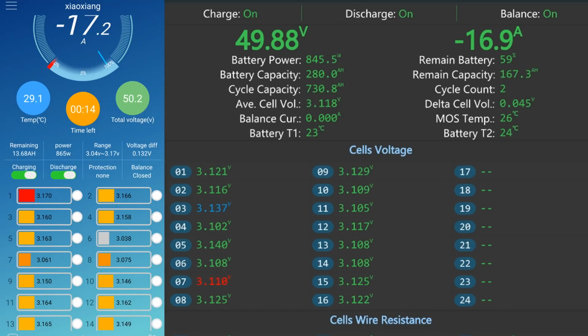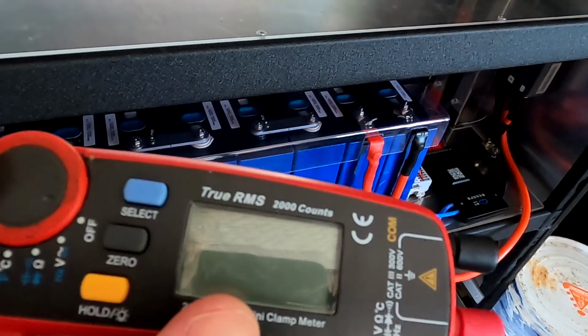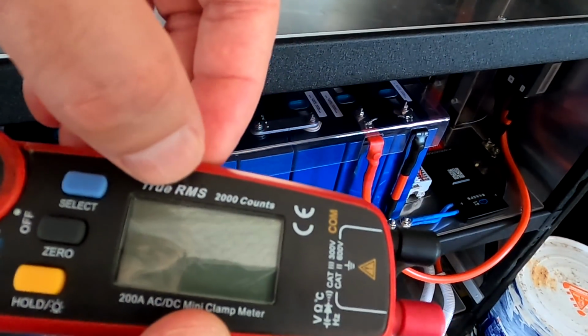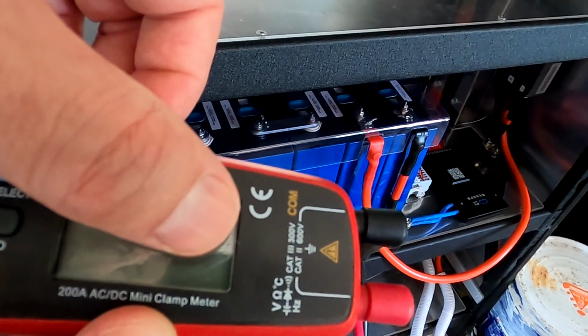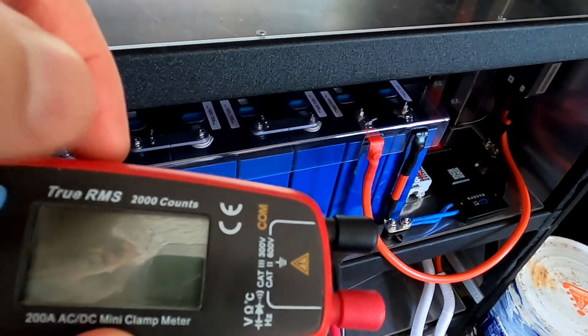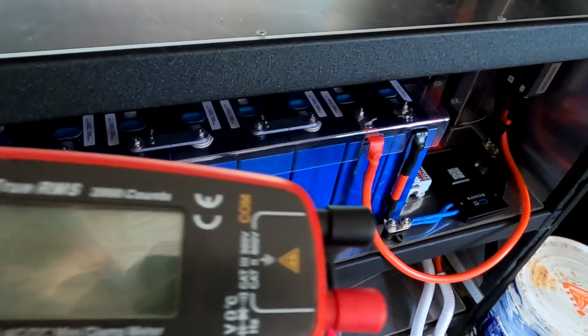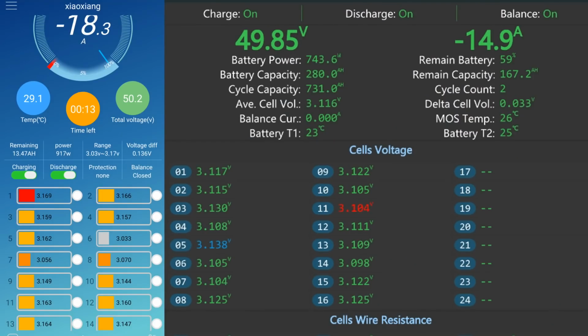Up North and Personal left a great comment under one of the last videos and explained actually why this is. It is because your normal voltmeter, your normal multimeter has true RMS, root mean square. That means this multimeter measures an average over a certain period of time and shows the value in the display. So if you have a very, very quick spike in your voltage, for example, this one will not pick it up, but will build an average. So your voltage goes up and down slowly. The JK-BMS on the other side does not have RMS measurement method. So this one shows you the true voltage at this moment.